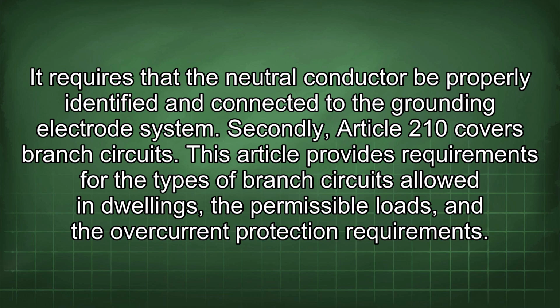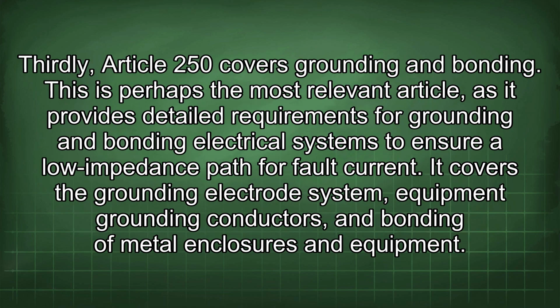Secondly, Article 210 covers branch circuits. This article provides requirements for the types of branch circuits allowed in dwellings, the permissible loads, and the overcurrent protection requirement. Thirdly, Article 250 covers grounding and bonding. This is perhaps the most relevant article, as it provides detailed requirements for grounding and bonding electrical systems to ensure a low impedance path for fault current. It covers the grounding electrode system, equipment grounding conductors, and bonding of metal enclosures and equipment.